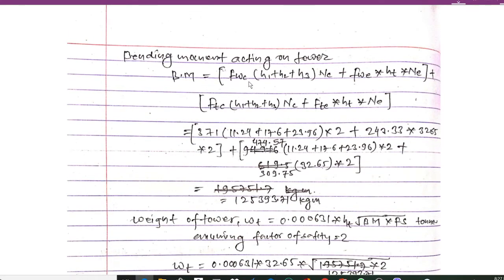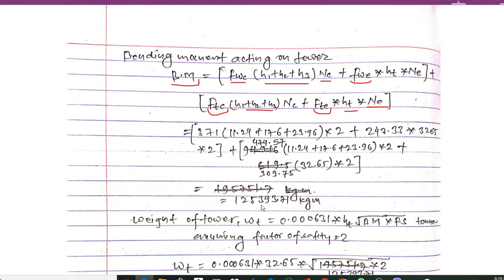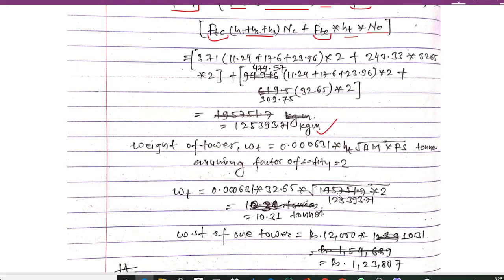The bending moment acting on the tower is: BM = FWC × (H1 + H2 + H3) × NC + FWE × HT × NE + FTC × (H1 + H2 + H3) × NC + FTE × HT × NE. Substituting all obtained and given values, the bending moment = 125393.7 kg·m.